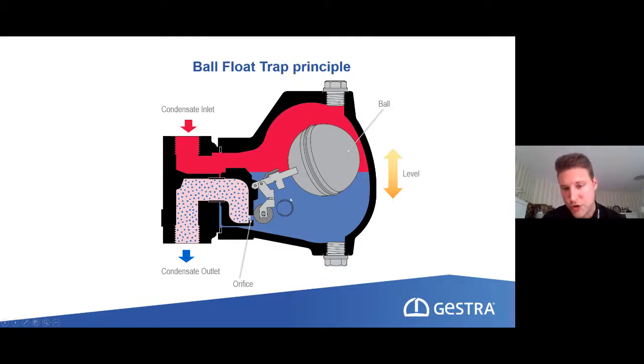so that the flash steam can leave the steam trap. And here with the design, you already see that a ball float steam trap is very much unaffected by dirt, because we have a lot of room here, a lot of space, so that dirt will not affect the operation. This is a valuable thing, especially for dirty processes where we usually know there's a lot of dirt inside, we have to change something. But here we have a lot of space for that.